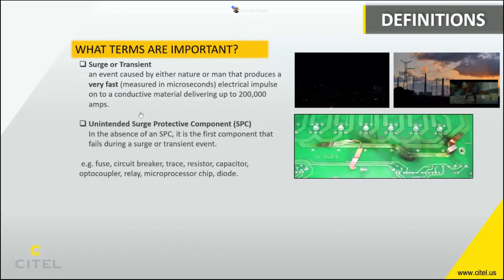Let's take a look specifically at a circuit breaker, which is an unintended SPC. It's commonly used in place of a surge protector, and a lot of people mistakenly believe it offers some surge protection. It really doesn't. Maybe it's because someone reset a tripped breaker after a storm and thought it helped the equipment.